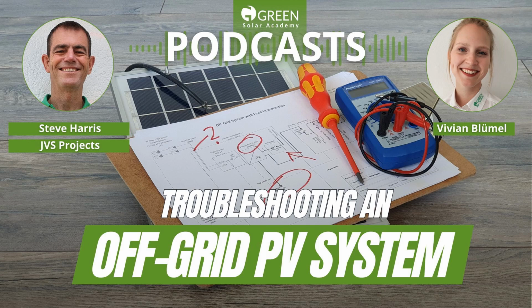So we would then start connecting things back together, mostly with the inverters, and there are exceptions, but I'll use this as our standard thing. We would connect the batteries onto the inverter. And without anything else on, we'll have a look and see what the inverter says. Is it telling us that the battery is low? Is it telling us that there's an issue?